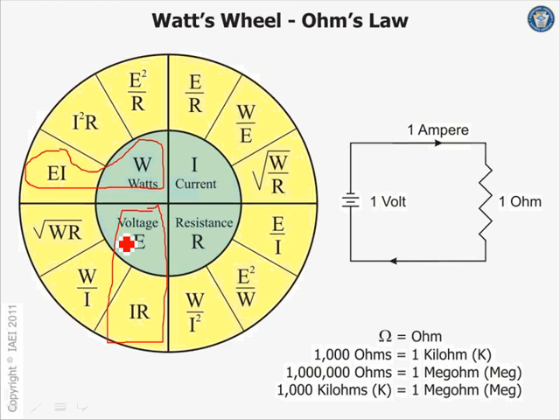That's how the power works, and the reason why they start you guys with this is because grounding and bonding is a circuit. It's called the safety circuit. So at one time, you're going to have this resistance in the ground path. You have to have this conductor large enough to facilitate the operation of the overcurrent device, meaning to allow bigger current to go right through it fast enough so that the circuit breaker trips before you burn your building. Right? Does it make sense that your circuit breaker trips after you burn the building or before? If you don't care about the circuit breaker tripping after the fire truck pulls in, then you don't have to worry about the grounding and bonding.